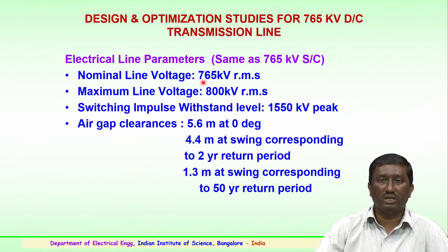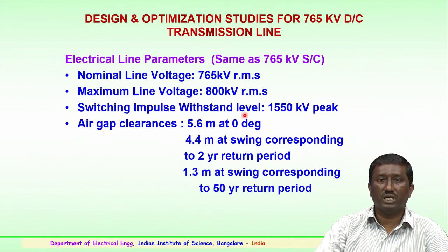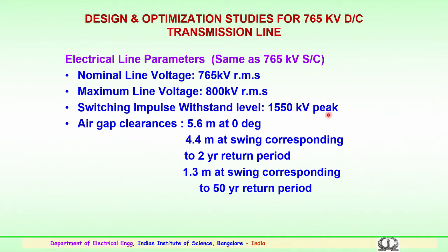The nominal voltage was 765 kV and maximum operating voltage was 800 kV. Switching surge similar to single circuit was 1550 kV peak. Air gap clearances were 5.6 meters at 0 degrees, 4.4 meters at swing corresponding to a 2-year return period, and 1.3 meters at swing corresponding to a 50-year return period.